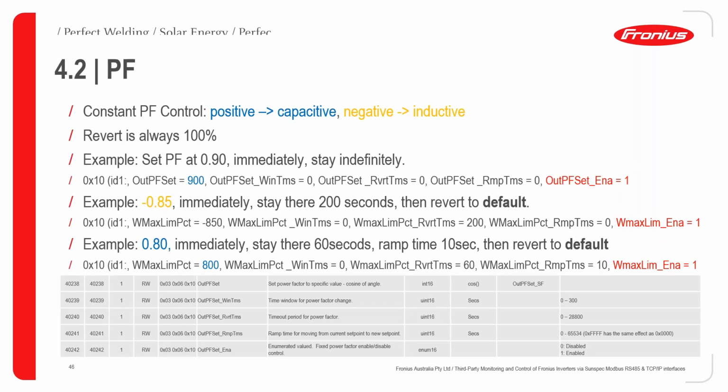Similar situation for controlling the power factor as well. It will be a block of 5 registers. I would say, if not copy paste, but very similar to the one said previously. One thing to point out, you can always have positive or negative power factor, which means positive will be capacitive, negative will be inductive. Something to think of when you do your implementation.